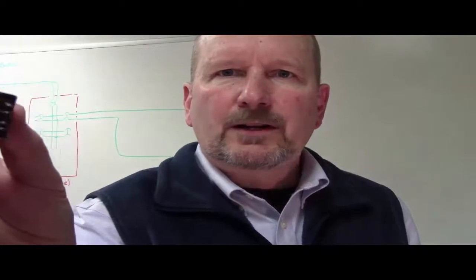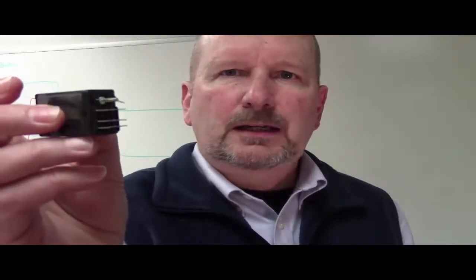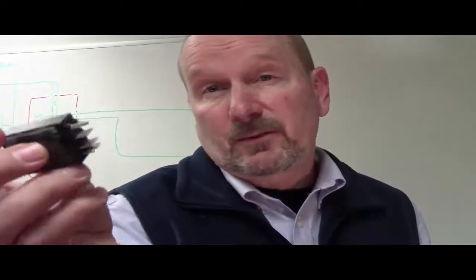Now then, as I said, I've got three examples of auxiliary relays, and the first one is real small, and I refer to this as a little flash cube relay. You actually don't wire to this relay, you wire to a plug that has terminal blocks on it, and then you stick this into the plug. And if you happen to damage it, it makes it real easy to replace. But you can imagine that these things have very low duty contacts because they're very small. However, they're still the same basic components that we'll find in the larger one that I'm about to show you.